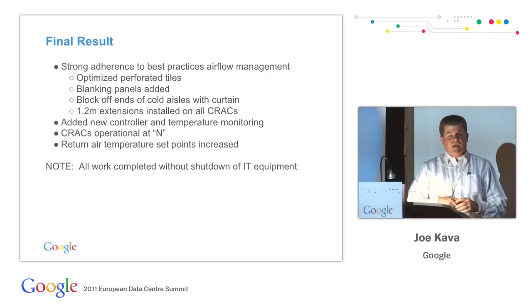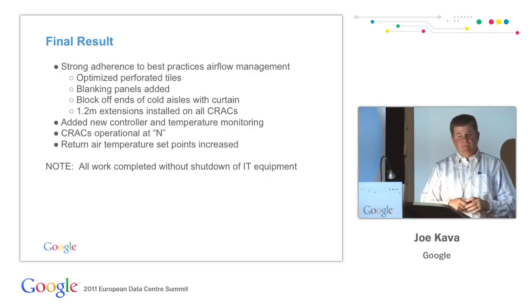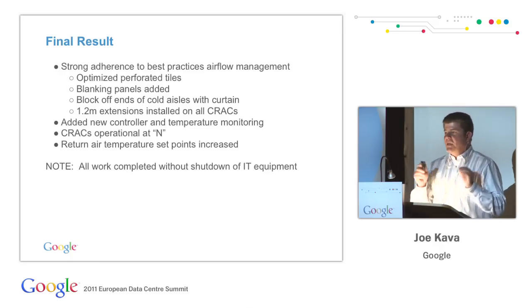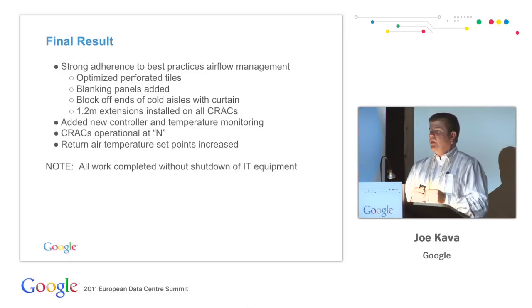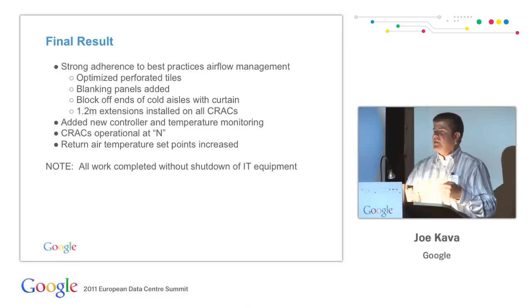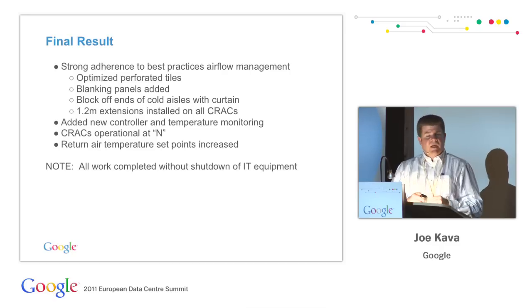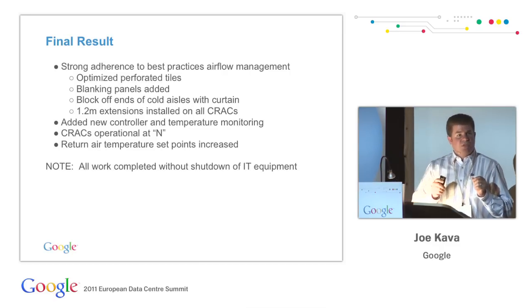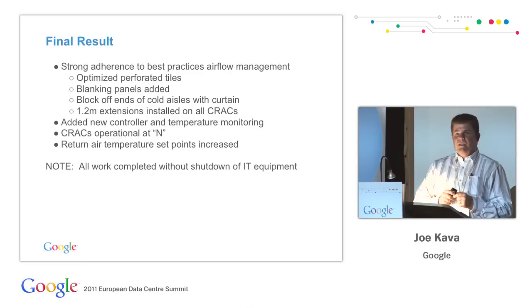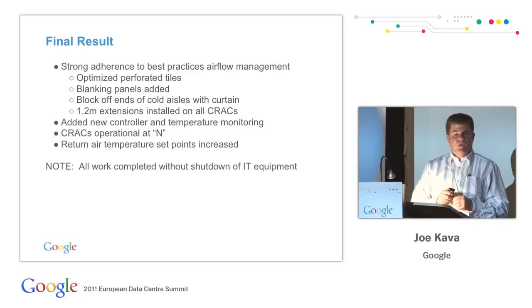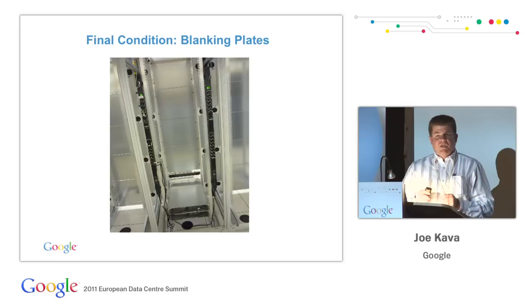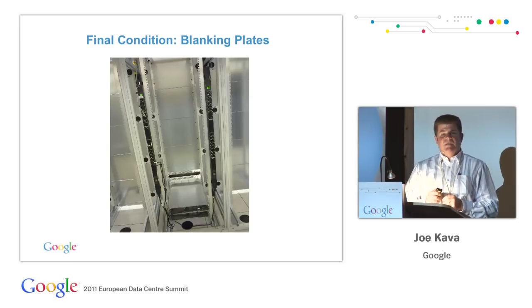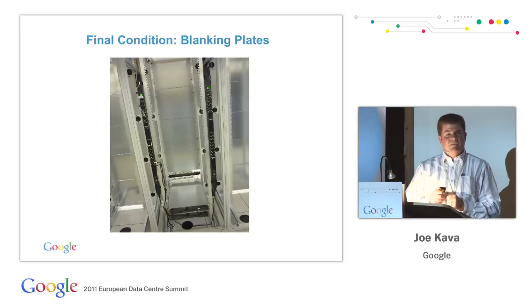As I mentioned, we had blocked off all the cold aisles with containment. You'll see some pictures of the freezer sheets, the plastic meat locker curtains. And all of this work was done without any IT equipment shutdown. So this was all done on live operating network rooms. So here are some pictures. Of course, blanking plates, pretty simple, not very sexy, but pretty effective.